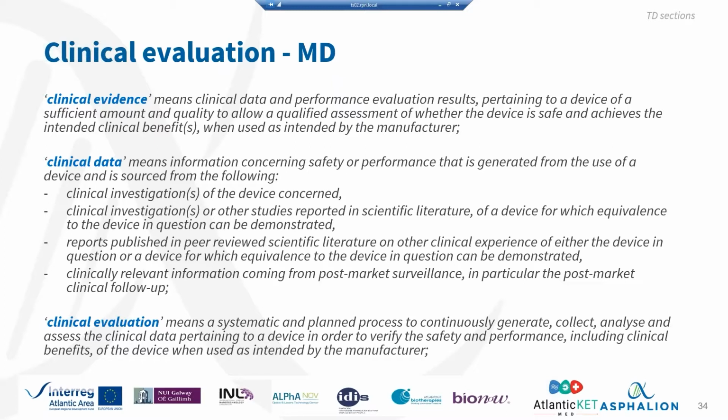complying with the safety and performance. Then clinical data: we can all imagine what clinical data is, but let's clarify that it means information concerning the safety or performance that is generated from the use of a device and is sourced from clinical investigations. Let's remember that clinical investigations is the terminology for clinical studies in medical devices. Clinical investigations of the device concerned, or other studies reported in scientific literature. This also can be used for your clinical evaluation.